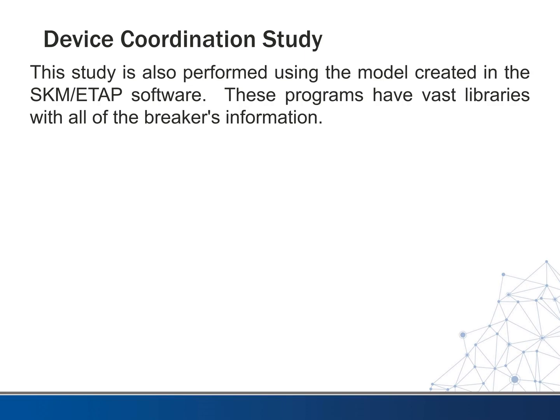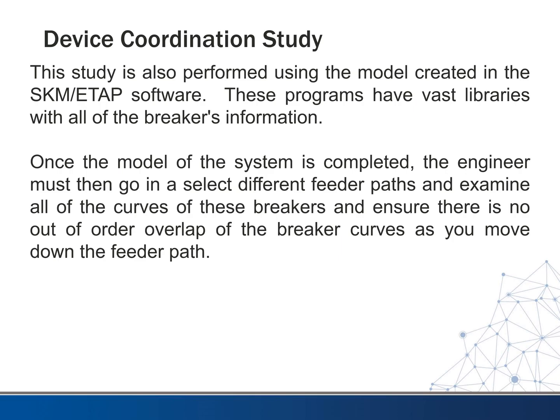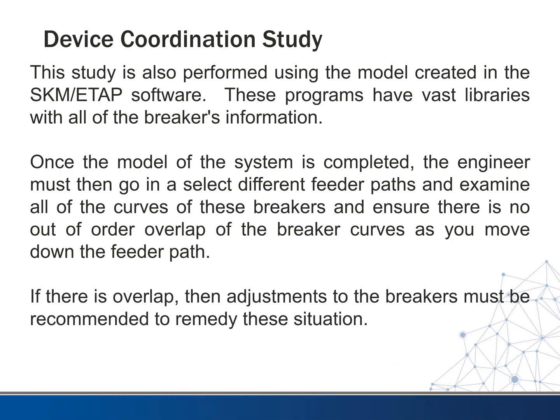This study is also performed using the model created in SKM or ETAP software. These programs have large libraries with all of the breakers, buses, and wire information. Once the model of the system is completed, the engineer must go in and select different feeder paths throughout the system and examine all the curves of the breakers in each path to ensure there's no out-of-order overlap — you don't want your main breaker tripping before a breaker down the line would. If there is overlap, the engineer works to make adjustments to the breaker settings to ensure the right breaker trips first.